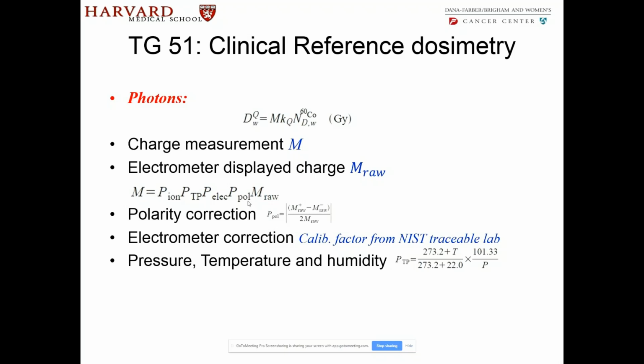TG51 actually is valid within a relative humidity range of 20% to 80%. If it is extremely dry or extremely humid, the suggestion is don't do TG51, wait for another day, or in some way or the other fix the humidity in the room.